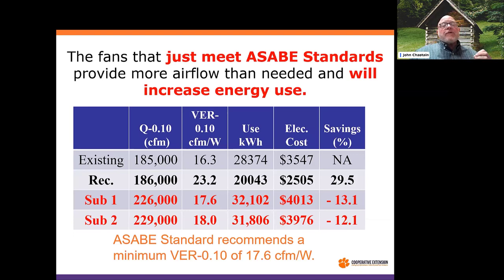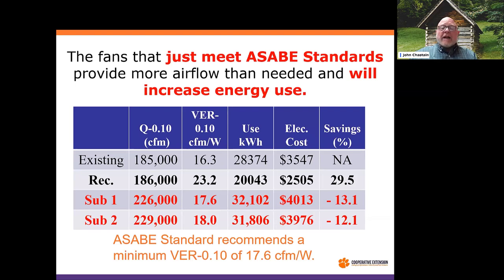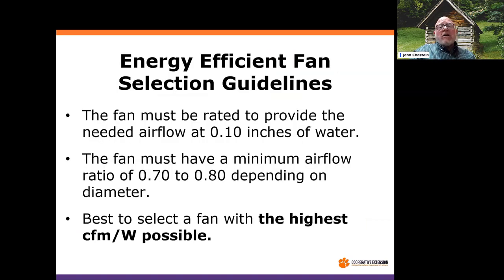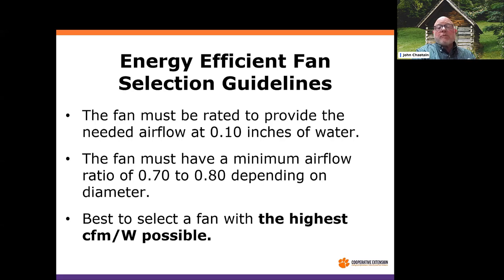One caveat: if a facility needs to increase airflow to meet certain guidelines, we want to do that in the most efficient way possible — and many times the goal is to break even on cost while meeting new ventilation requirements. To summarize the guidelines for fan selection: fans must be built well for ag environments; they must provide the required airflow at one-tenth of an inch static pressure; they must meet minimum airflow ratio requirements — 0.7 to 0.8 depending on diameter; and you want the highest CFM per watt you can get, because that will keep saving money for the life of the fan.